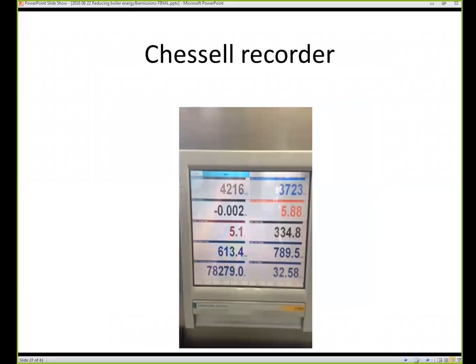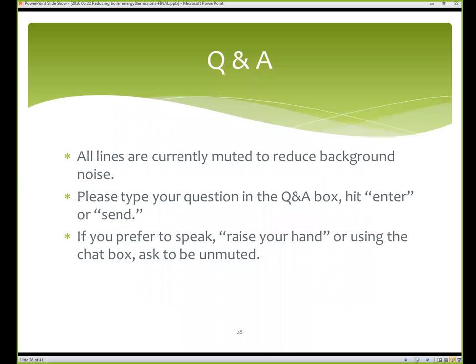Next down, this is a paperless recorder, and it will show you the amount of steam you're using, how much gas is going through the transmitter, your O2, your stack temp, your total. This is a really, really good recorder. We have a computer program that goes up to that on that previous screen, and we record all that information on the hard drive. It logs it, so it records it. I went through this kind of fast, and I don't know if that's exactly what you were looking for, but hopefully it's a few hints on what we do.